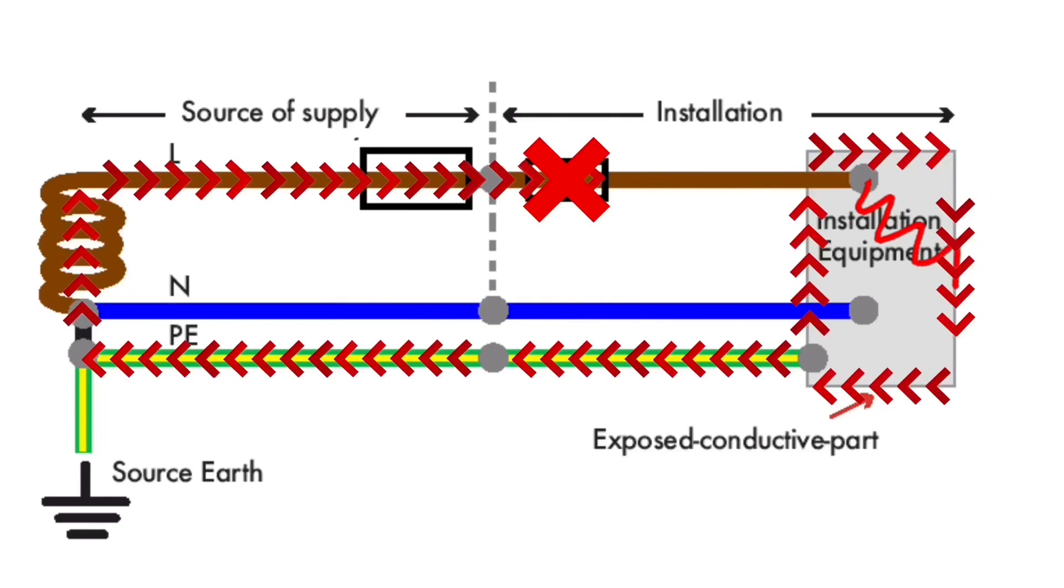We looked at two maximum times for disconnection: either a maximum time of 5 seconds or a maximum time of 0.4 seconds. I have described to you the earth fault loop path for an installation connected to a TNS earthing arrangement.